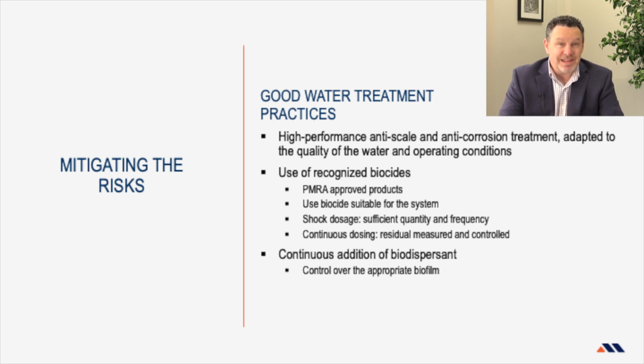So what we're trying to do is mitigate them and reduce them. At the basic level, what we need to do is ensure that you have in place a proper scale and corrosion program for your cooling water. Make sure it matches with your water qualities, your operating temperatures, your volumes, your metallurgies. That's really important to do. It has to be at a basic level. You need an effective water treatment program for that.